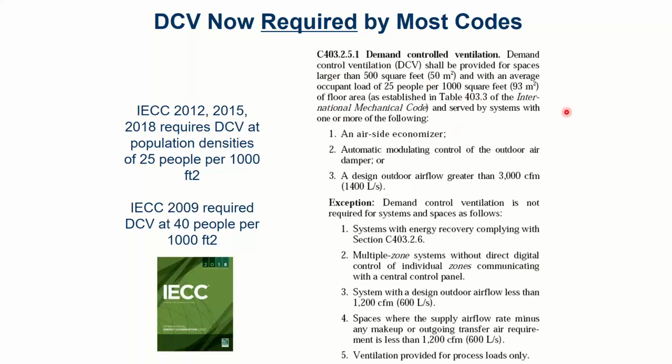What does that mean? That means classrooms, movie theaters, conference rooms. If you have offices with really small cubicle area, like you have a bunch of these 6x8 little cubicles for like a call center or something, you probably have the density where you're going to have to do it. You have something bigger with giant private offices where each person has their own 15 by 15 office. You're not going to have to do it.